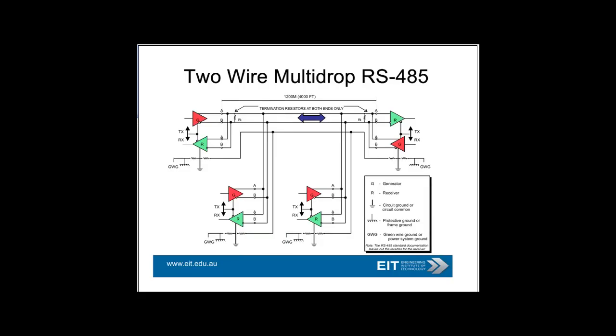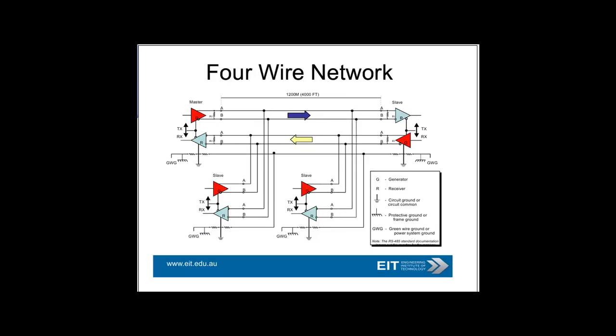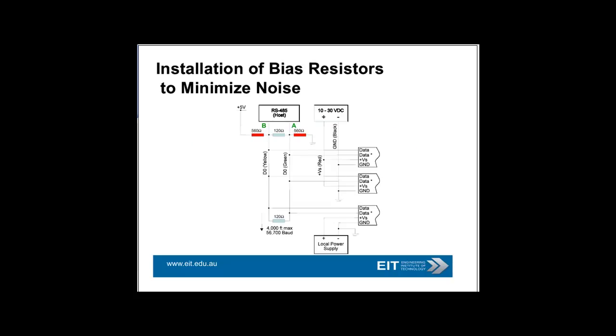Here's a typical example of an RS-485 network. One of the issues is to put in termination resistors to prevent reflection. Also, the other issue is to ensure your grounding is done properly to avoid common-mode voltage problems. Here's a four-wire network, and obviously there's the matter of minimizing noise.